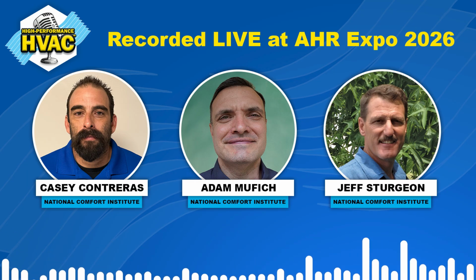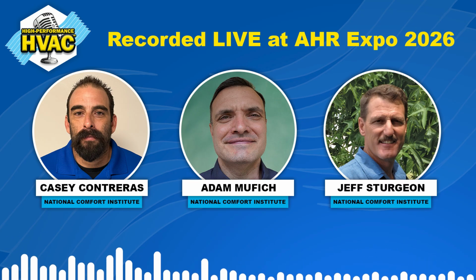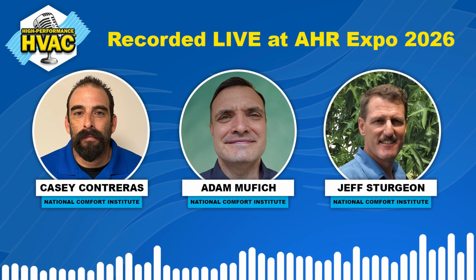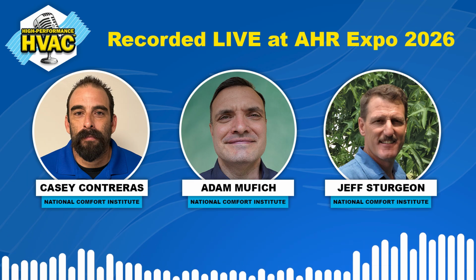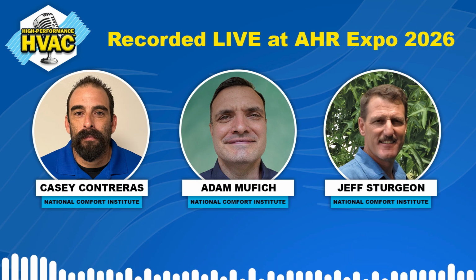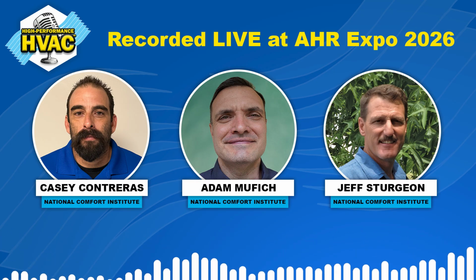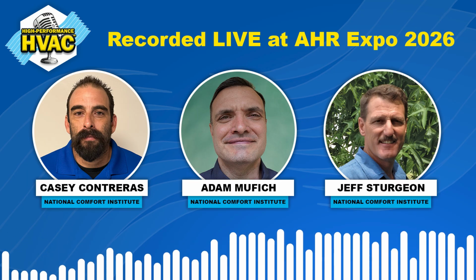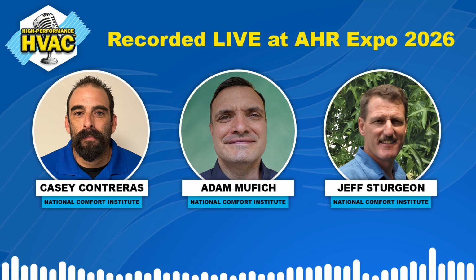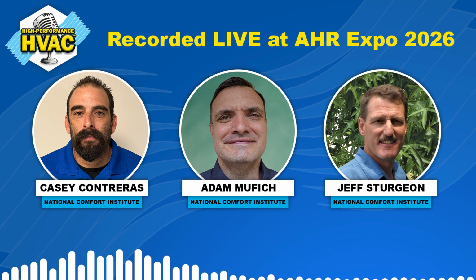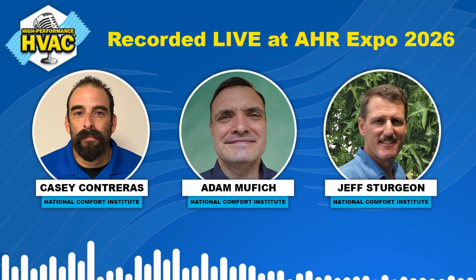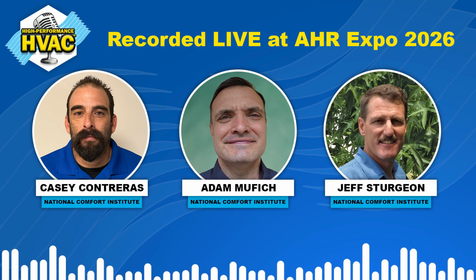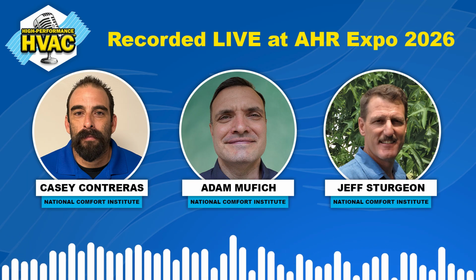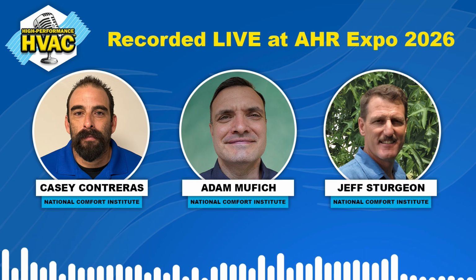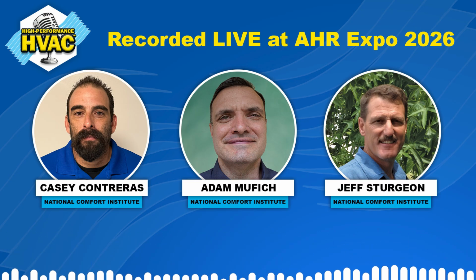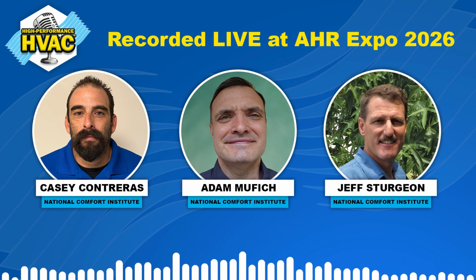So that's the big disconnect. It's partly an engineering standpoint, but also sensor placement and equipment orientation. If the equipment is oriented so the hot afternoon sun beats on the side where I'm planning to install sensors, I'll put them on the other side instead, so they're not influenced by radiant heat transmitted through the metal surface. Otherwise the temperature reading could be as much as 50 degrees off actual. Those blower panels don't have much insulation.